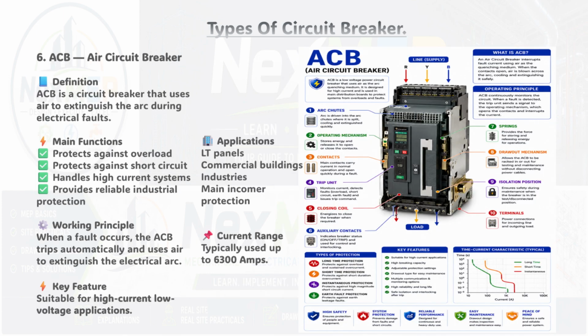Next up is the ACB, the air circuit breaker. This is a heavy-duty breaker used for high current, low voltage applications. So what makes ACB special? When a fault occurs, whether it's an overload or a short circuit, the ACB trips automatically. And when the contacts open, air is blown across the arc, which cools it down and extinguishes it. That's why it's called an air circuit breaker. Air is the arc quenching medium.